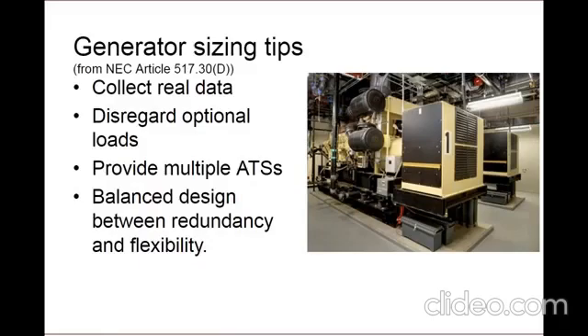So having this data is crucial if you want to use those exceptions that Rob talked about in Article 517.30(D) when sizing your generators. That's where you're permitted to use the actual demand likely to be produced on the system as opposed to the connected load demand. So this method of calculation facilitates practical sizing of generators in healthcare facilities to help eliminate operational problems associated with lightly loaded generators. So some basic tips on generator sizing is to collect real data from past facilities after at least 12 months of operation.